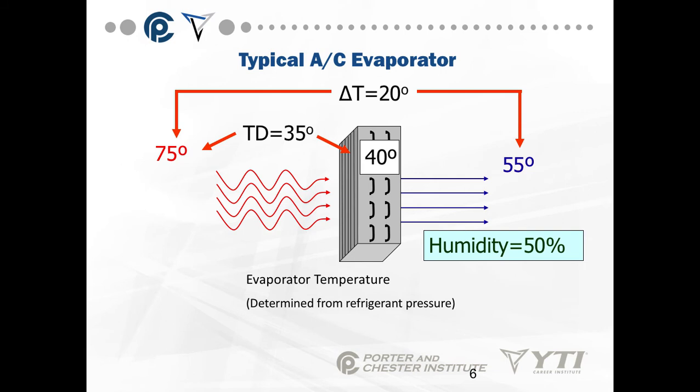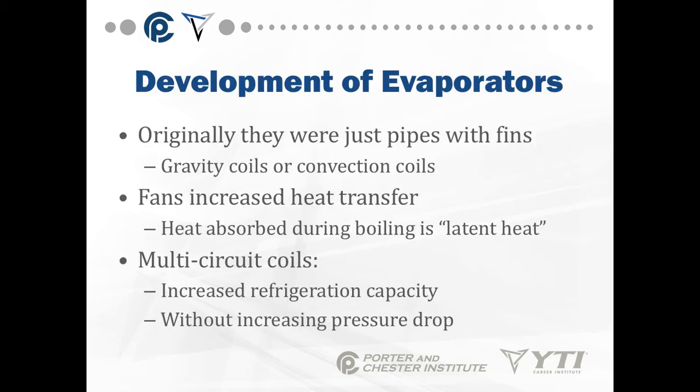With 50% humidity, one of the things our evaporator has to do is remove humidity. Originally, evaporators were just pipes with fins — gravity coils or convection coils. Fans increased heat transfer. Heat absorbed during the boiling process of refrigerant is latent heat. Surface area and capacity were increased by folding the coils over, using multi-circuit coils, making coils longer with more surface area without increasing pressure drop.